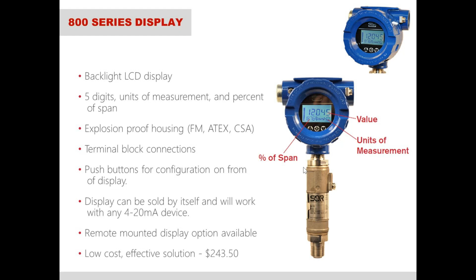The housing that it comes in is an explosion-proof FM, ATEX, and CSA-approved explosion-proof housing. It also acts as a junction box, having terminal blocks and connections on there as well. It has a push-button display, so that you can push the buttons to change the assigned values for the 4 milliamp and the 20 milliamp signal. However, note that the push buttons on the display will not translate to changing the output of the actual transmitter itself.